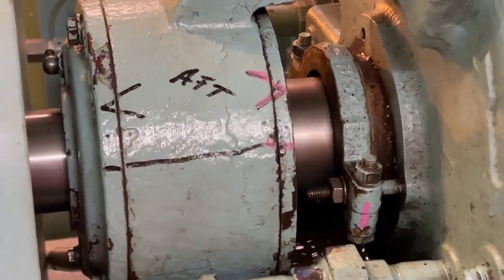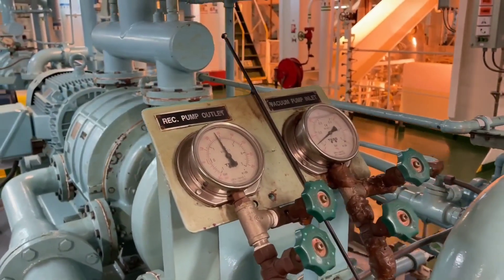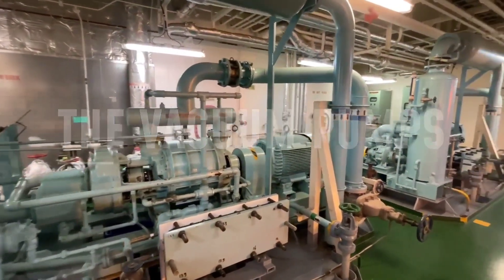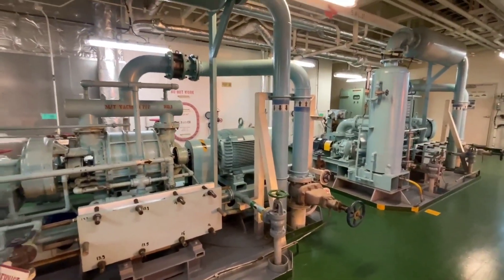Vacuum gets naturally generated due to condensation of steam, but to maintain high vacuum, we have to continuously remove incondensable gases by vacuum pump. Hence, the vacuum pump is a critical machinery. The steam plant won't be able to run optimally without the vacuum pump.